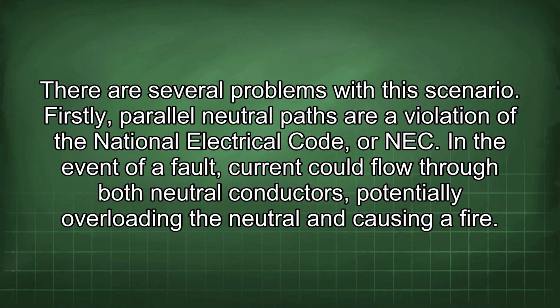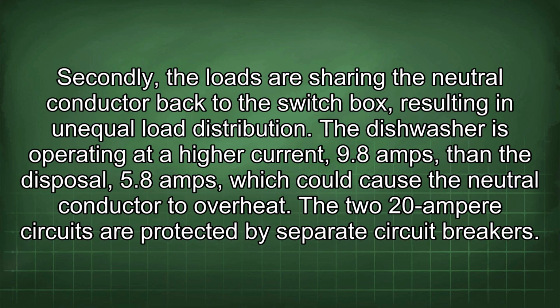There are several problems with this scenario. Firstly, parallel neutral paths are a violation of the National Electrical Code, or NEC. In the event of a fault, current could flow through both neutral conductors, potentially overloading the neutral and causing a fire. Secondly, the loads are sharing the neutral conductor back to the switch box, resulting in unequal load distribution.